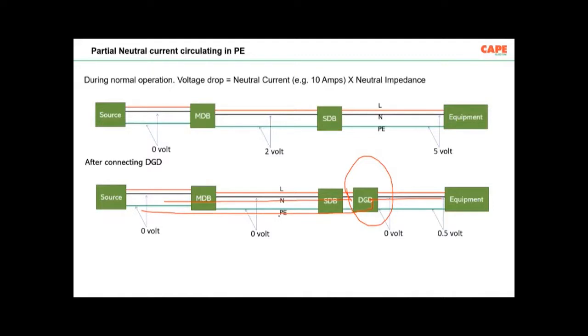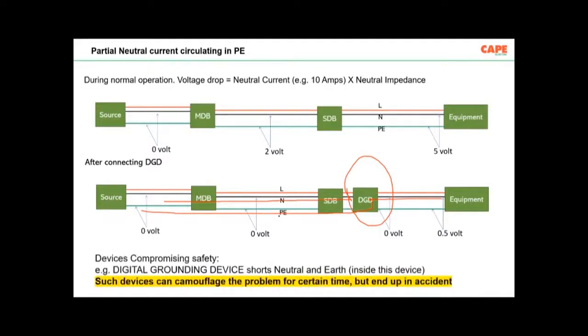So you are actually violating the electrical safety system. Now, these kind of devices or any shorting between neutral and earth in an installation is deadly. Please don't do it. You can connect neutral to earth only at one place, strictly at the source. After that, your neutral and earth must be separated. So if you make any connection, then your earthing is gone. Continuous current flow will happen through the earth conductor.